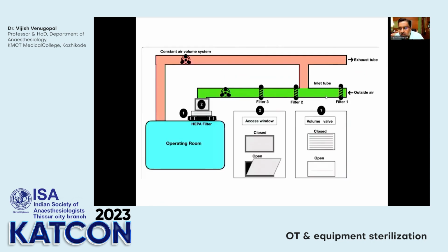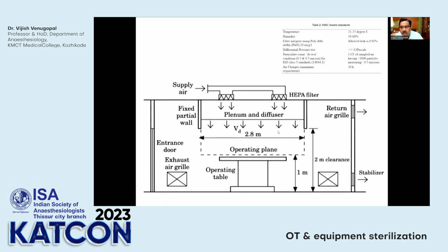And a few words on the AHU, that is the air handling unit. It consists of basically three parts. The first part is where air is taken inside, and there's a small filter there, and here it gets mixed with the recirculating air. From here it goes through a 5 micron filter into the next chamber where there is a condenser where the air is cooled, and then using a fan it is passed through a third filter, that is a 3 micron filter, and then it passes through thermo-insulated aluminum tubes into the HEPA filter, which is a 0.3 micron filter. And after that, it forms laminar airflow.